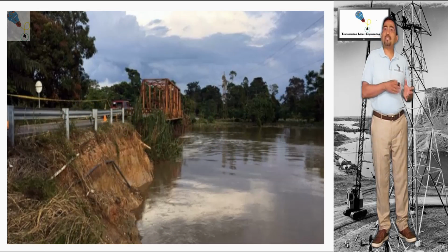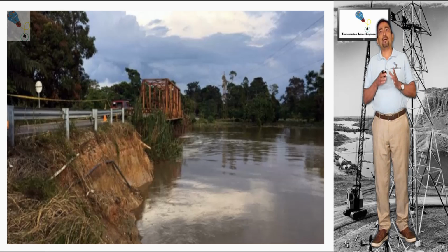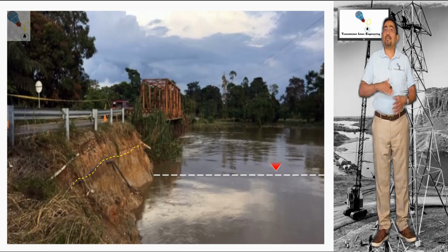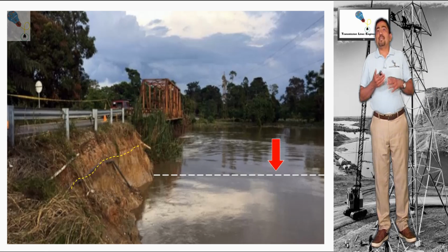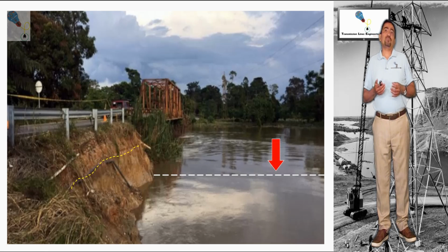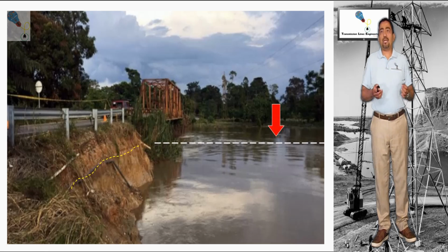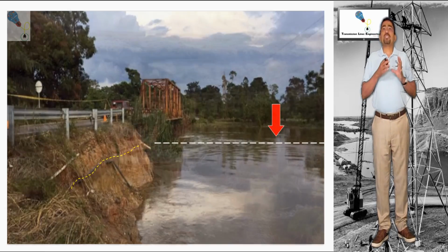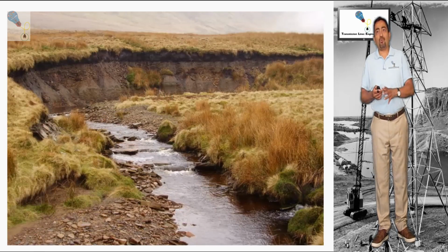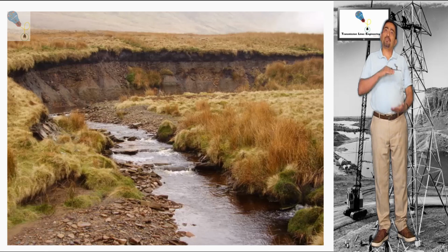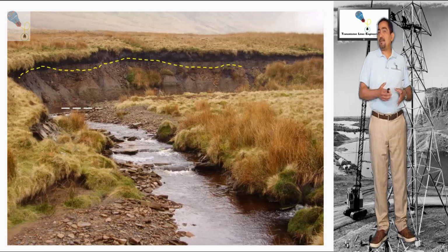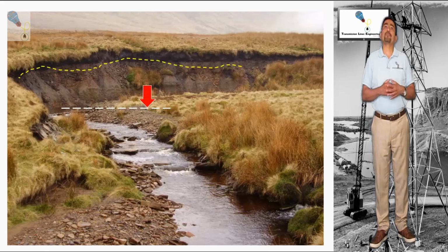Make a visual inspection of the undermining details at both ends, because here we can have an idea of how high the water level can rise, and this data is important for the designer of the transmission lines because it will set the origin point for the evaluation of the vertical clearances to the conductors. In addition, the crossing angle, as always, is required.